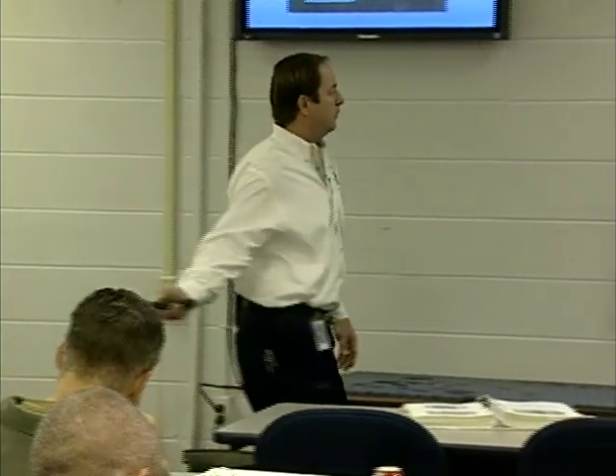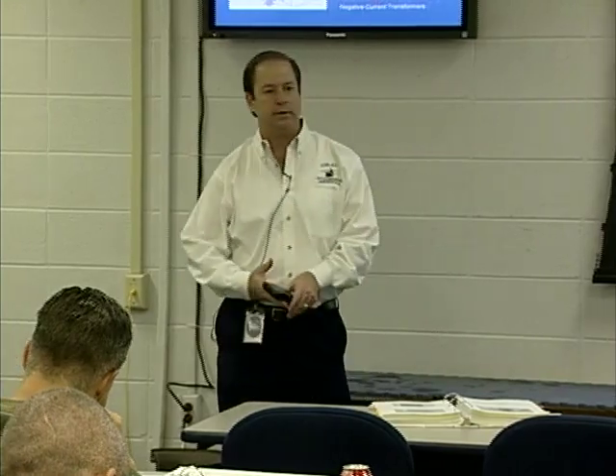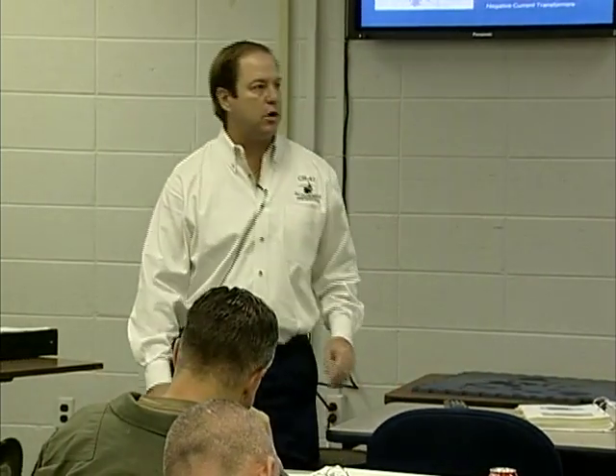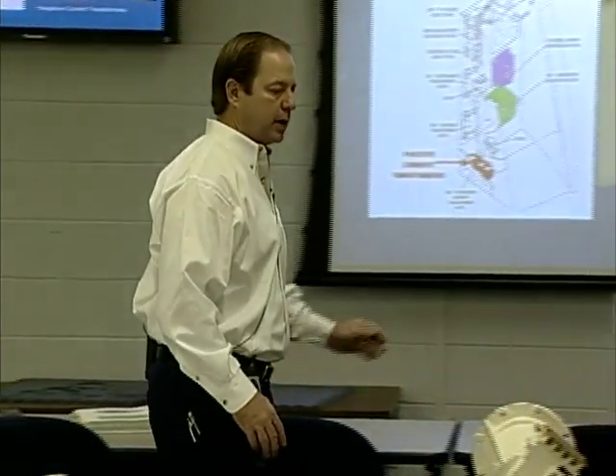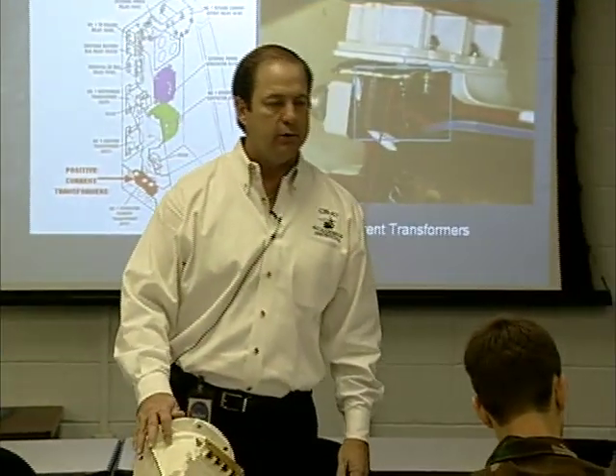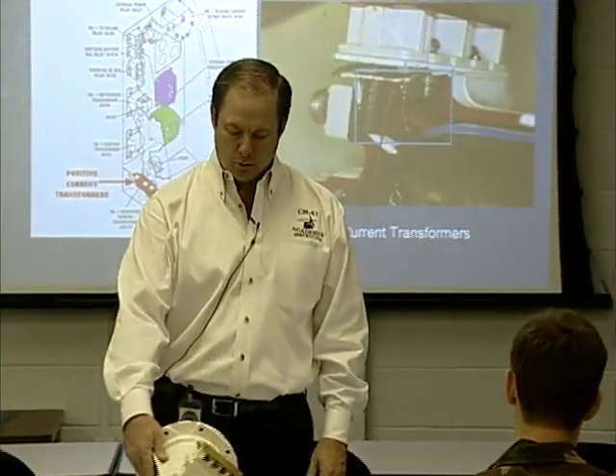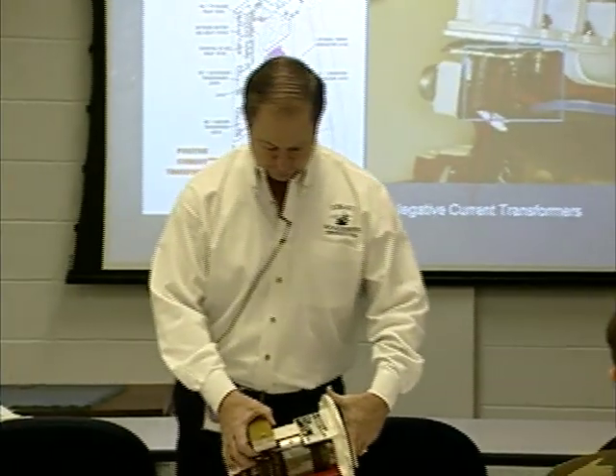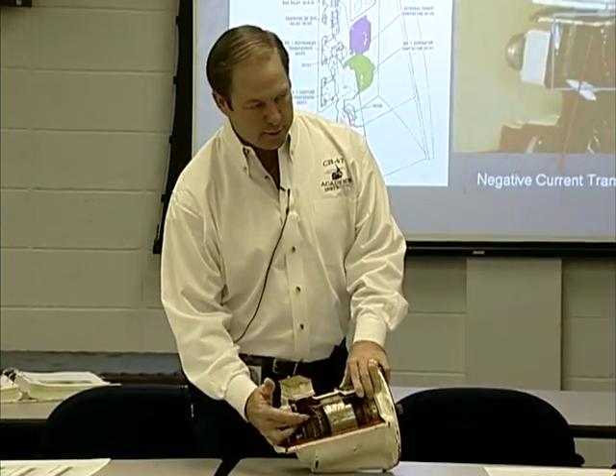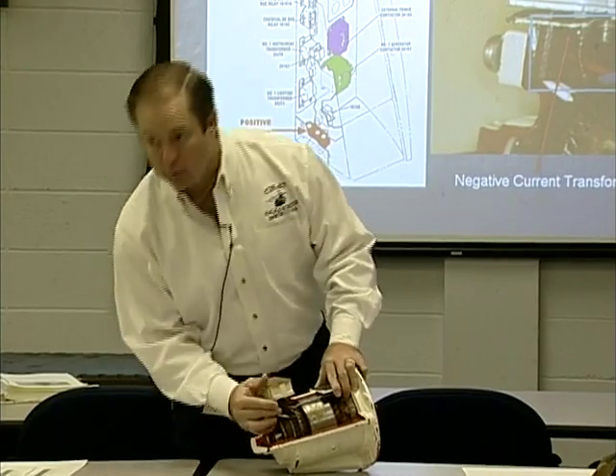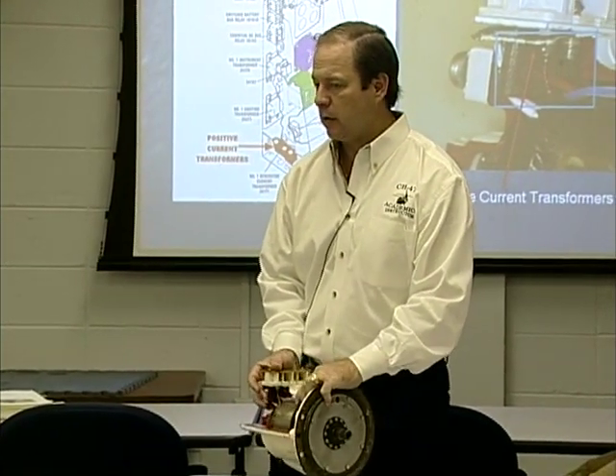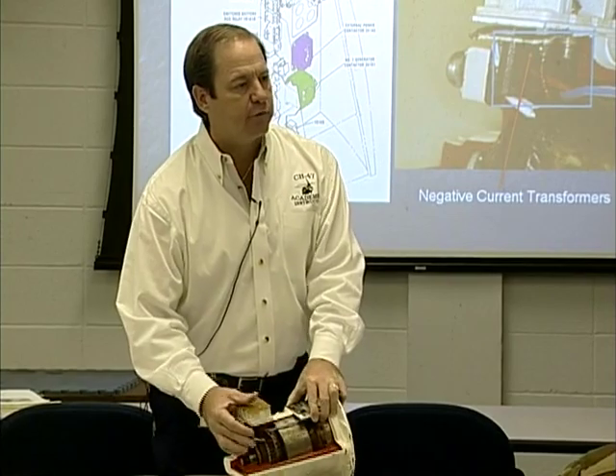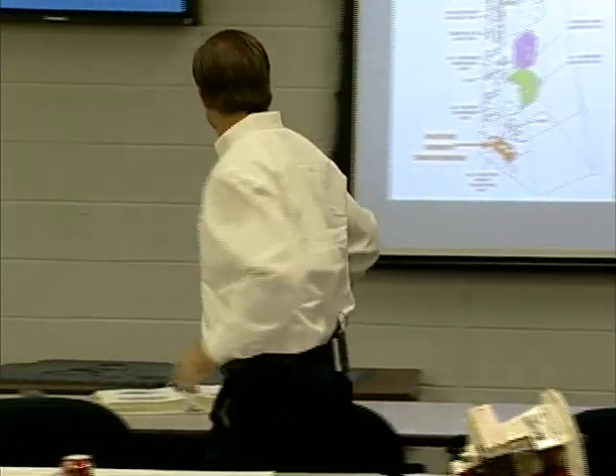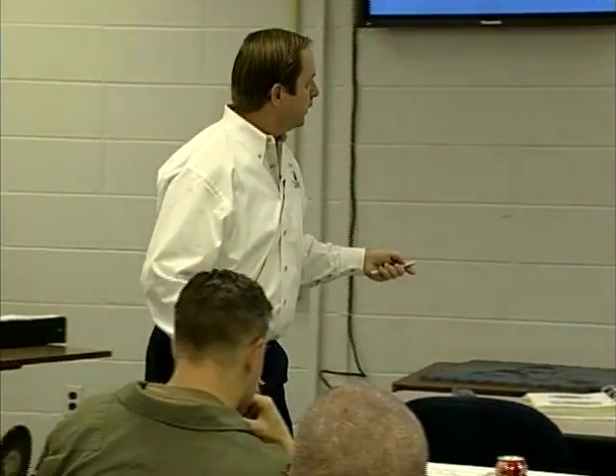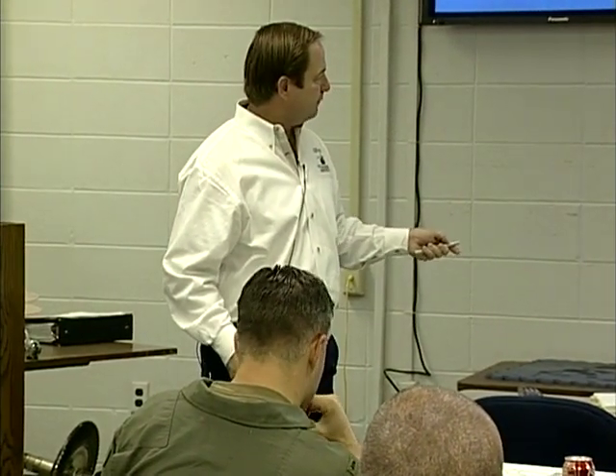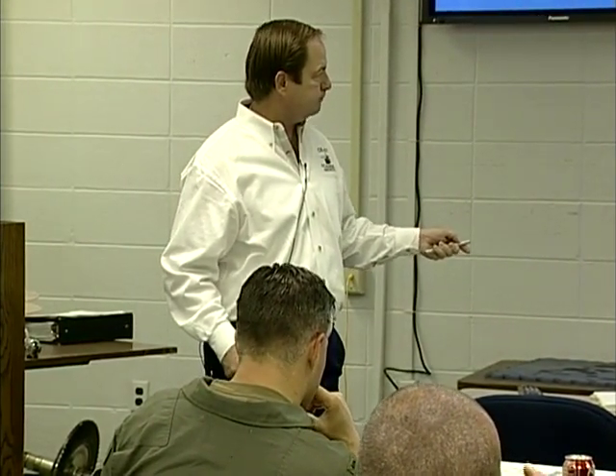Alright, now we're not done, because we talked about feeder fault, but now we need to talk about how feeder fault is detected. What you're going to find out, gentlemen, is right here — this is a component called a negative current transformer. I'll point them out; right here is a negative current transformer.